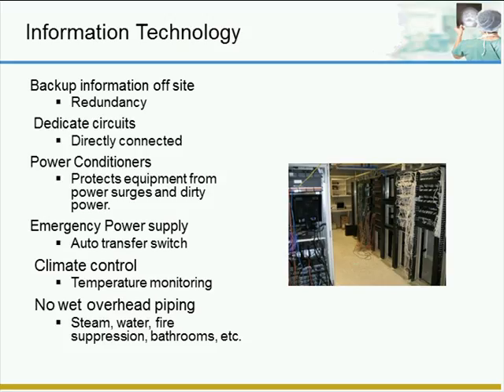IT rooms will typically be climate controlled. They'll have dedicated HVAC units with alarms. No wet piping overhead. You never want steam pipes, water lines, sprinklers, or bathrooms to have a failure and be dropping water onto your electrical equipment.